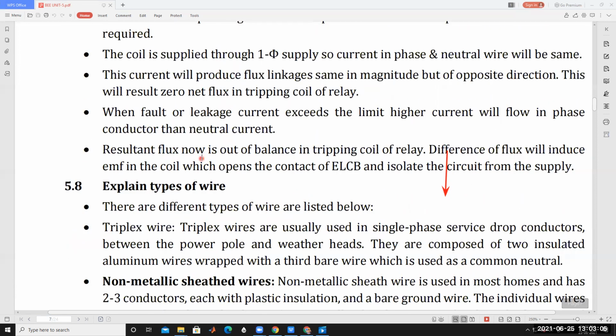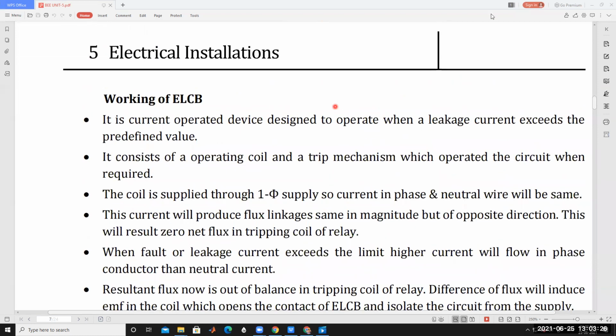Understood? The resultant flux is now out of balance in the tripping coil of the relay. The difference of flux induces an EMF in the coil, which opens the contact of the ELCB and isolates the circuit from the supply. So in this way, the ELCB operates. Is it clear?